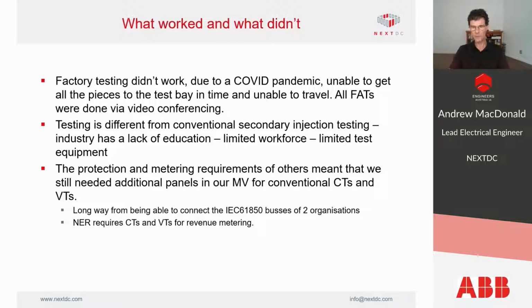The testing is very different from conventional secondary injection testing, and there's an industry lack of education and a very limited workforce with a limited amount of test equipment that knows how to test the sensors and the IEDs using the 61850 SMV signalling. We got around that somewhat by procuring the testing up front with our switchgear, but that also meant that we had limited vendors willing to tender.